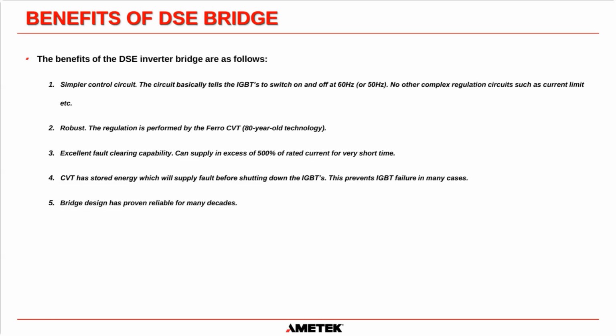I know that's hard to understand, but the transformer is designed in such a way that even if you put a short circuit on the output of a ferroresonant transformer, the inherent makeup of that transformer will prevent that short circuit from damaging the system, and it will limit the current into that short circuit. Number two, another benefit, is that it's robust. The regulation is performed by the Ferro CVT, which is 80-year-old technology. They've been around for ages, and they just work. They work all day, every day. Actually, I was just speaking to one of our service engineers last week, and he was at a system at a plant that is 40 years old, still running without any issues whatsoever. So they are very, very robust systems.